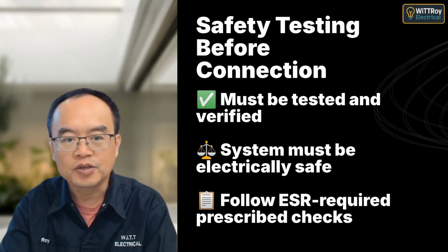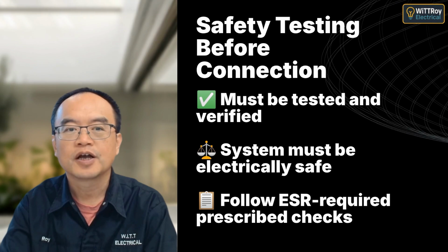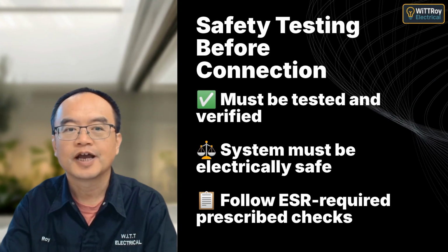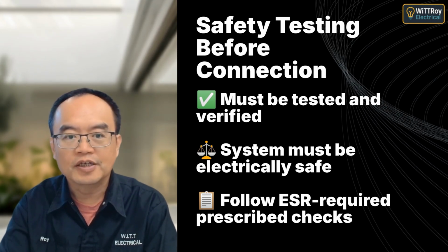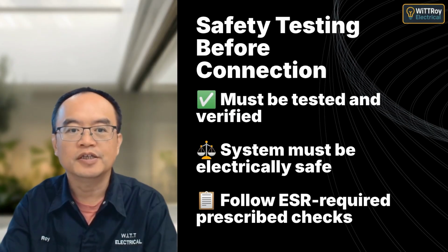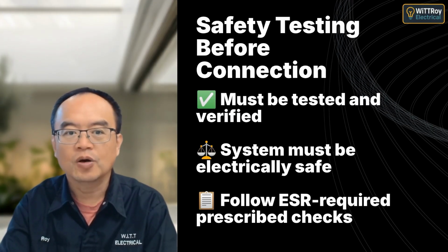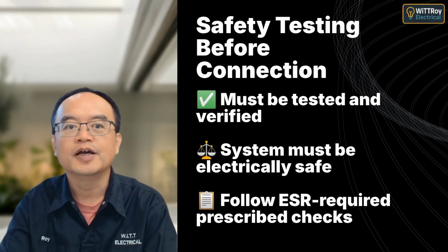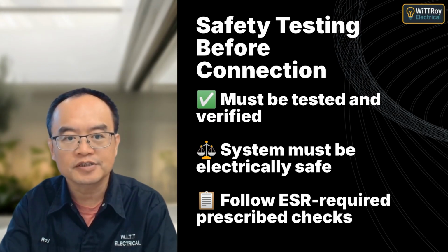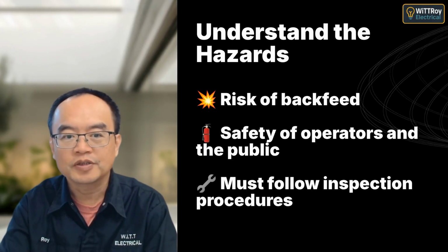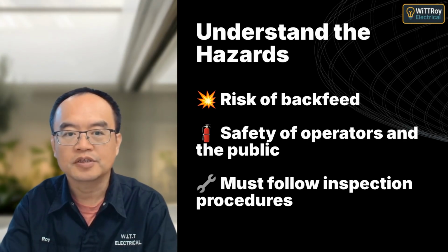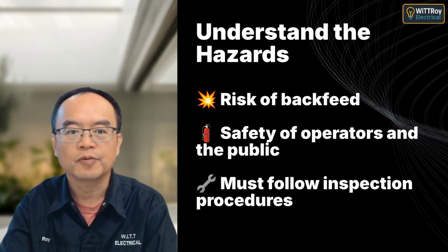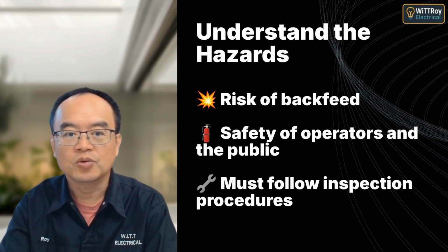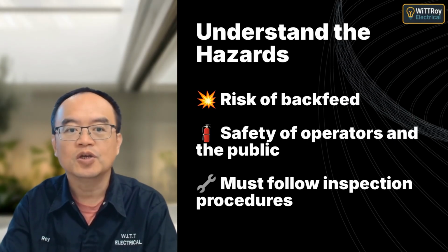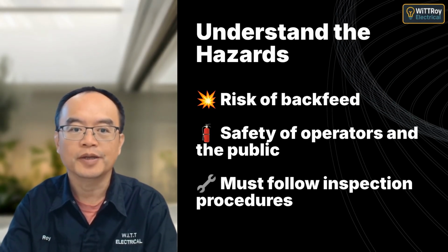Before a mains parallel generation system is connected to supply, ESR 73AE requires it to be tested and verified as electrically safe. This includes carrying out all required checks to ensure compliance and safety before energizing the system. When doing this kind of work, testing must be done to NZS 6116 and installation must meet the performance requirements of AS/NZS 3000 Part 2. This is a legal requirement under ESR 62B.